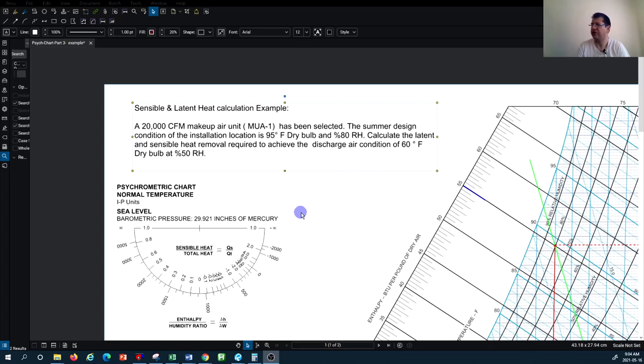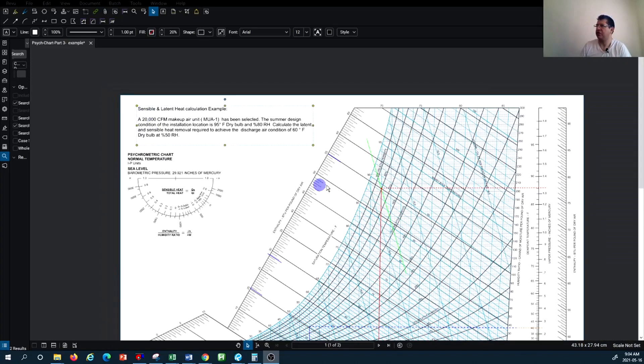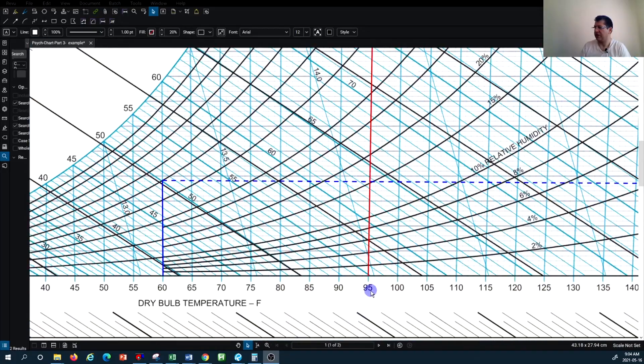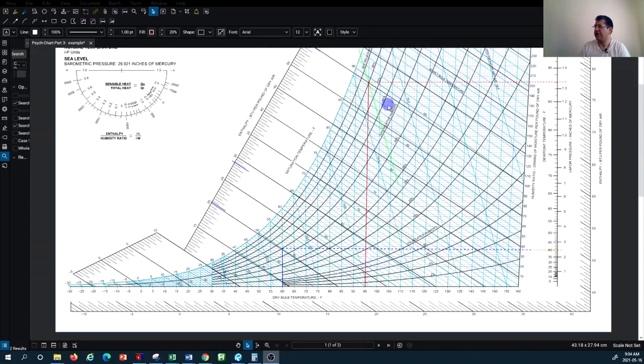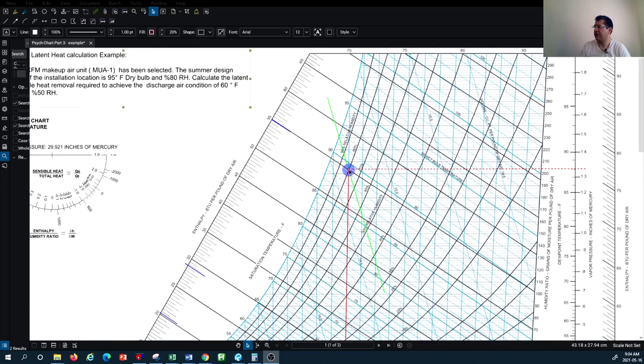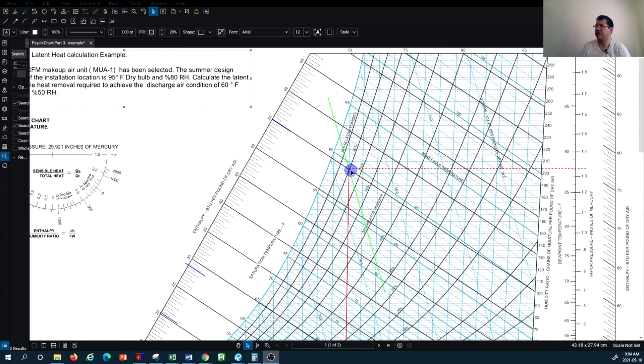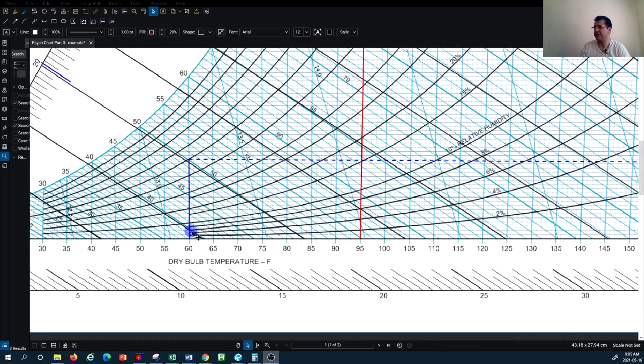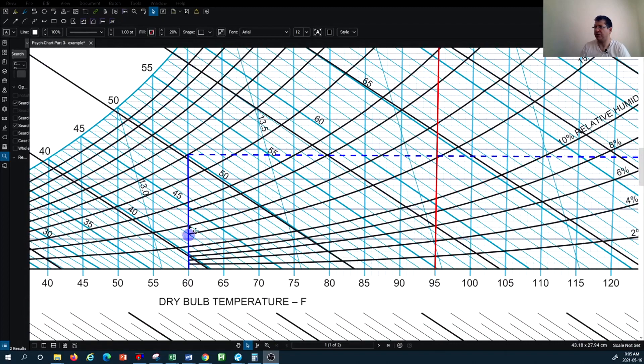We have two different points. The first point is the outdoor condition at 95 degrees Fahrenheit and 80 percent relative humidity, as you can see on this curve. We spotted the intersection location and identified the other parameters off that first point. The second point is the desired condition: 60 degrees Fahrenheit at 50 percent relative humidity.